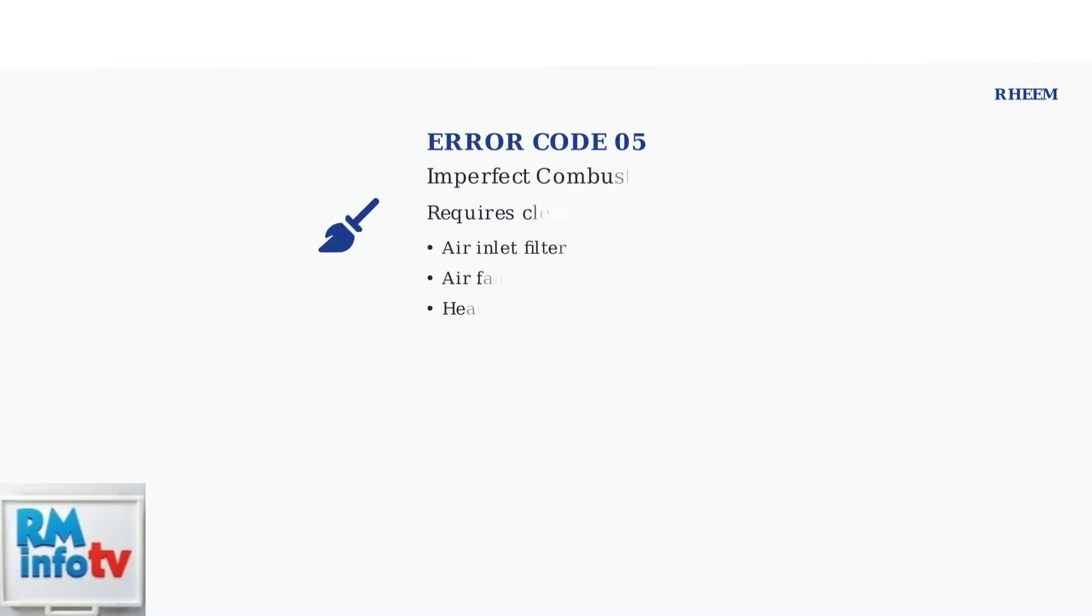Error code 05 indicates imperfect combustion. This requires cleaning the air inlet filter, air fan, and heat exchanger fins. Regular cleaning prevents this issue from occurring.